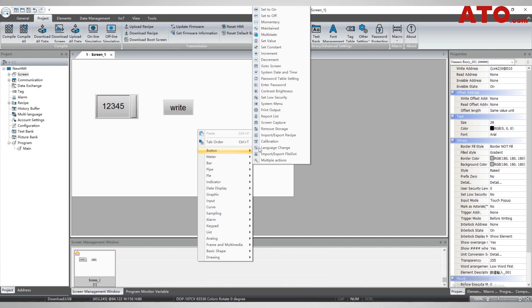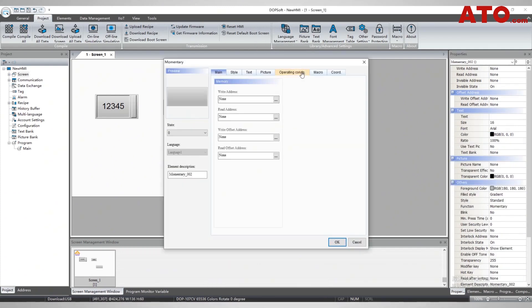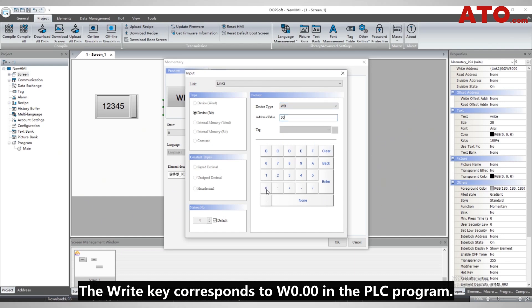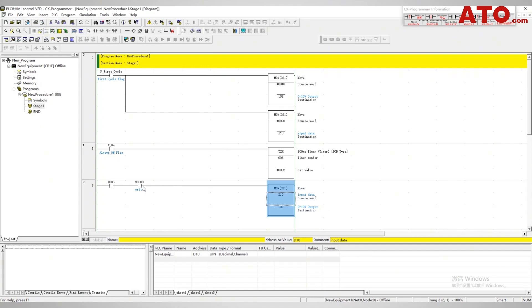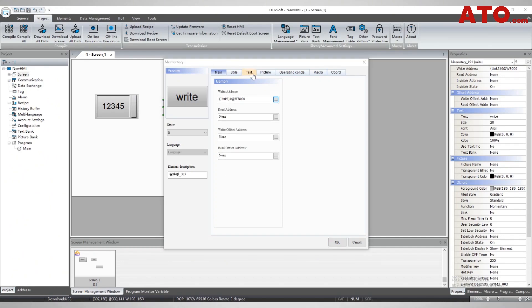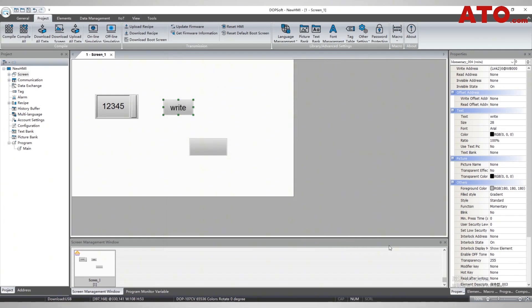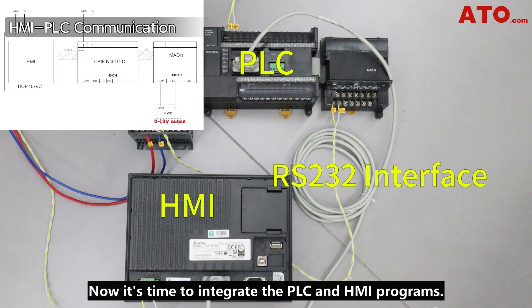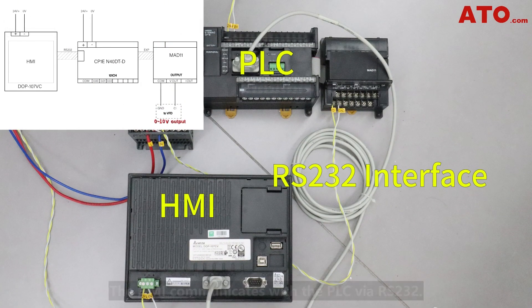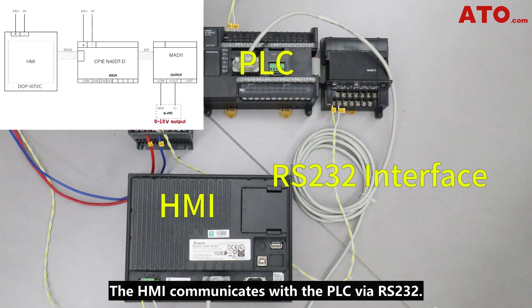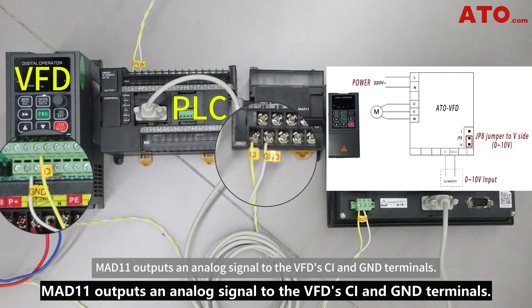Set the write key. The write key corresponds to W0.00 in the PLC program. Now it's time to integrate the PLC and HMI programs. The HMI communicates with the PLC via RS-232. MAD11 outputs an analog signal to the VFD's CI and GND terminals.